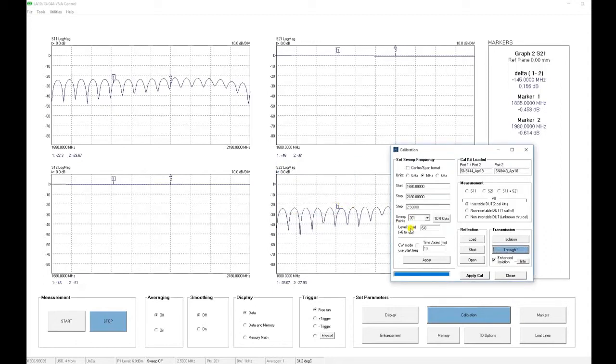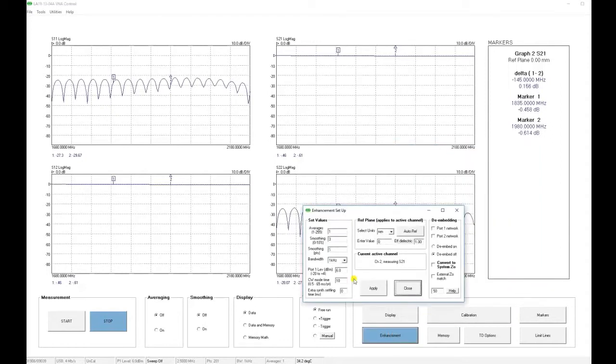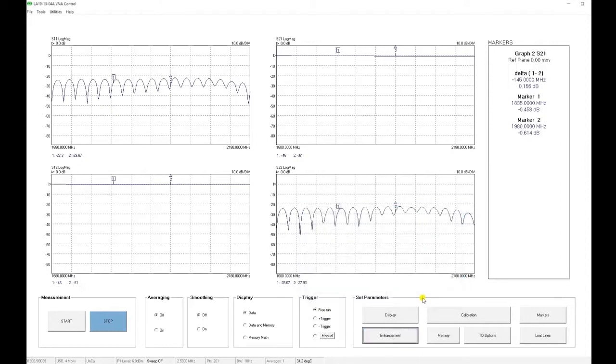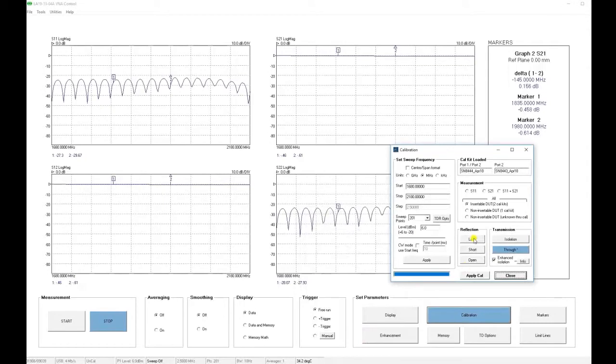Now, the rest of the calibration steps will be reflection measurements, and they need to be done at the lowest possible bandwidth. We close the calibration window just for a second, and set the bandwidth to 10 Hz. Now, we are ready to make the rest of the calibration measurements with a reduced bandwidth of 10 Hz.